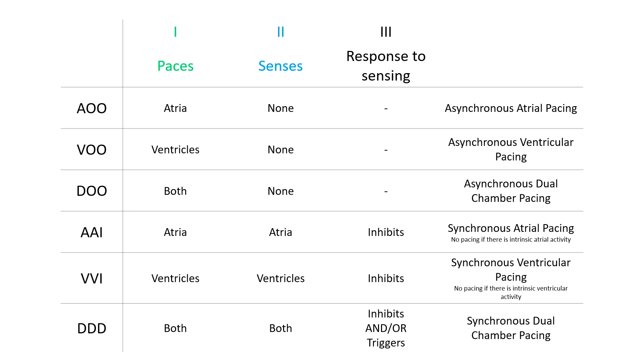These are some common modes used in temporary epicardial pacemakers. Pacing modes can either be asynchronous, like AOO, VOO, and DOO, or they can be synchronous, like AAI, VVI, and DDD. When a temporary epicardial pacemaker is in a synchronous mode, the pacemaker is able to listen for cardiac activity — this is called sensing. If the pacemaker detects cardiac activity in the relevant chamber, it will not fire an impulse to pace that region of the heart. Pause the video now to read more about these pacing modes.